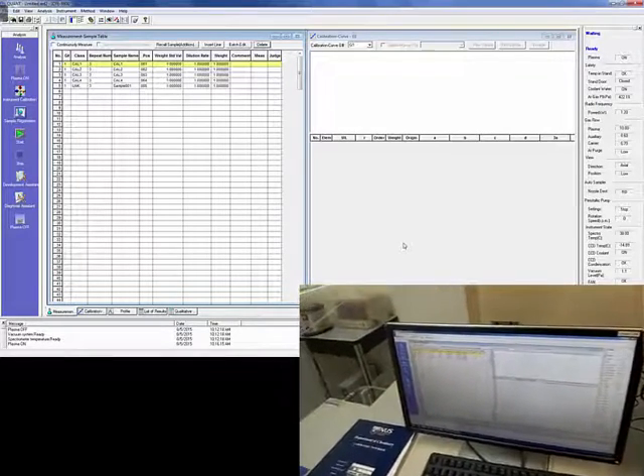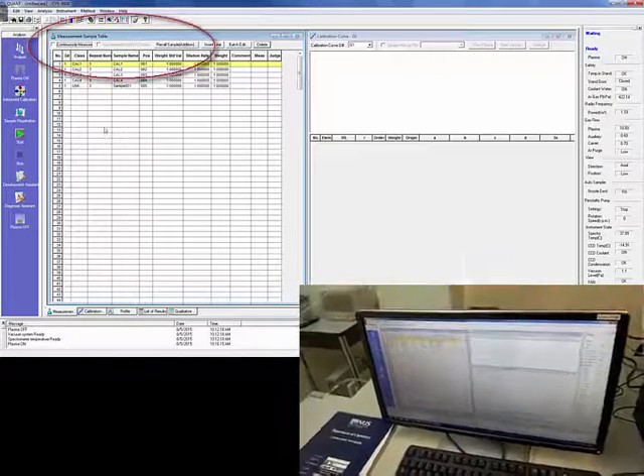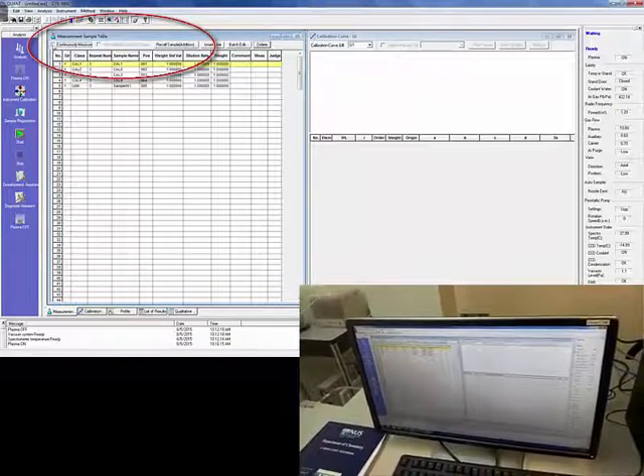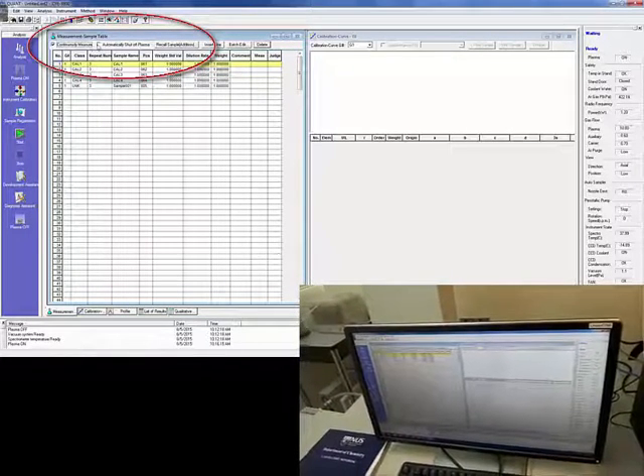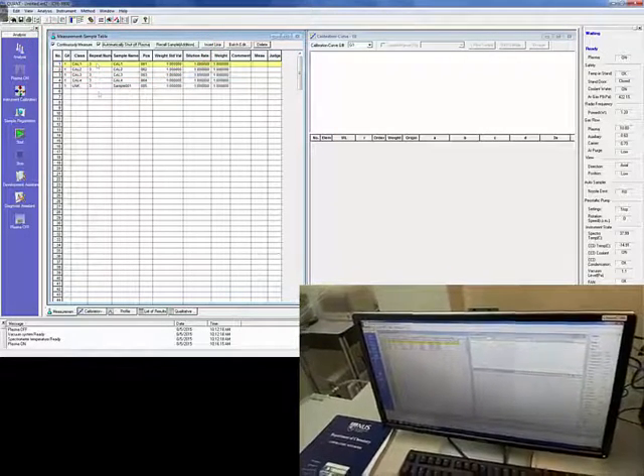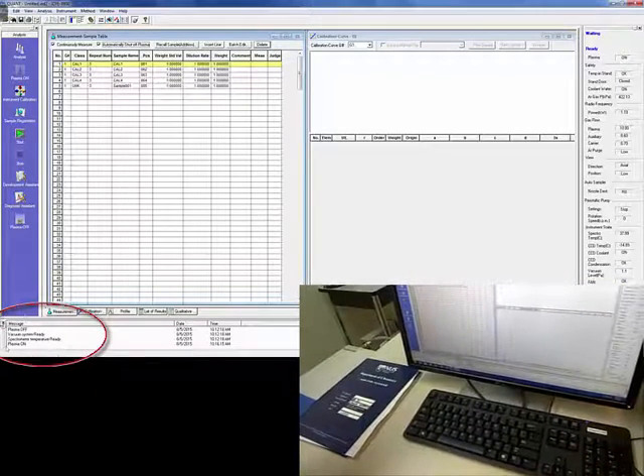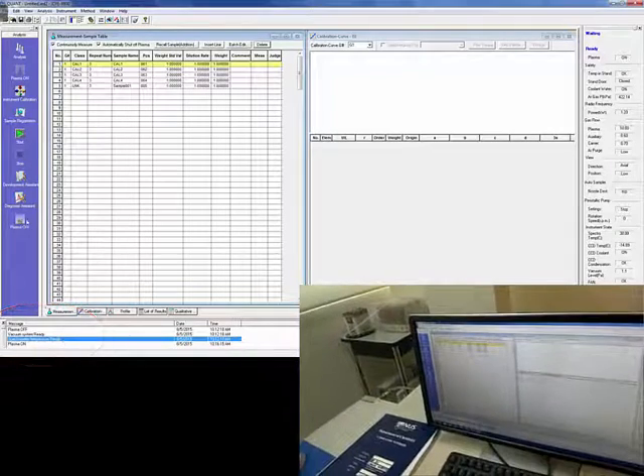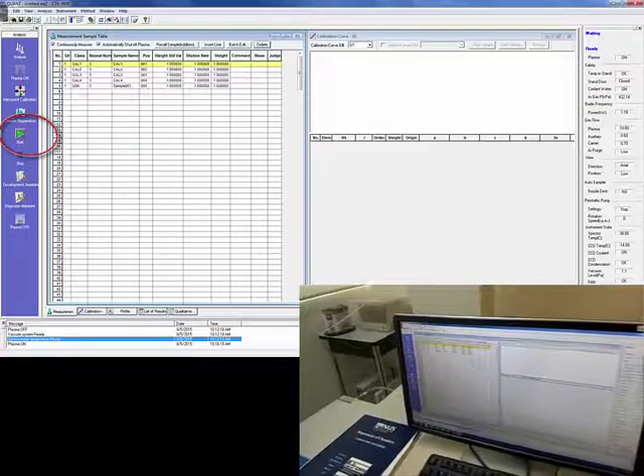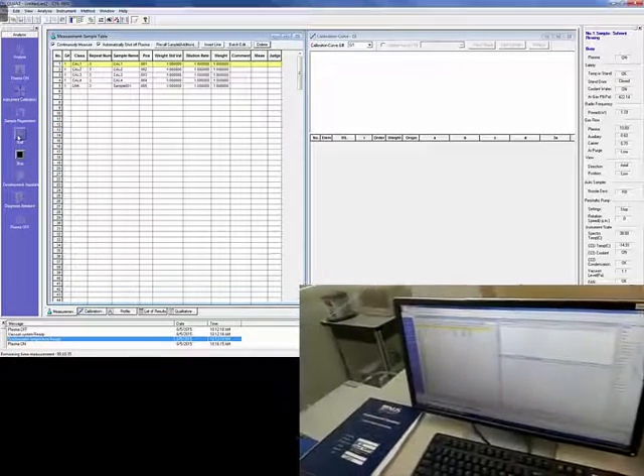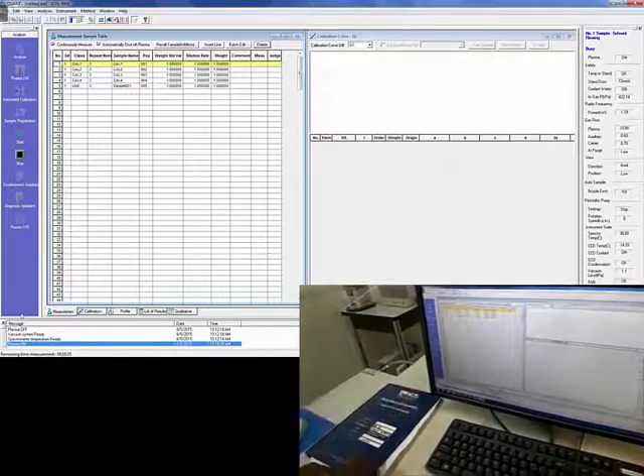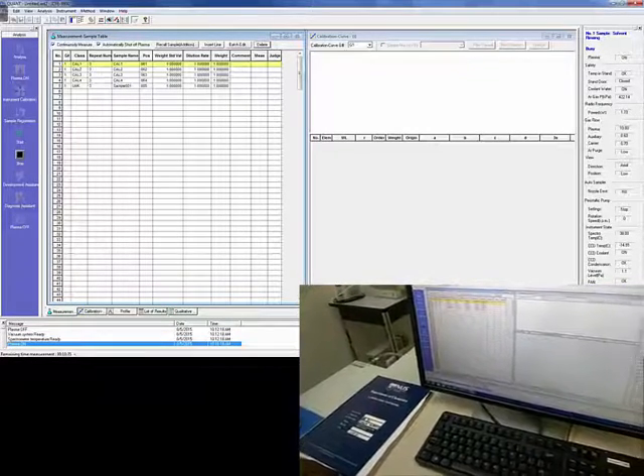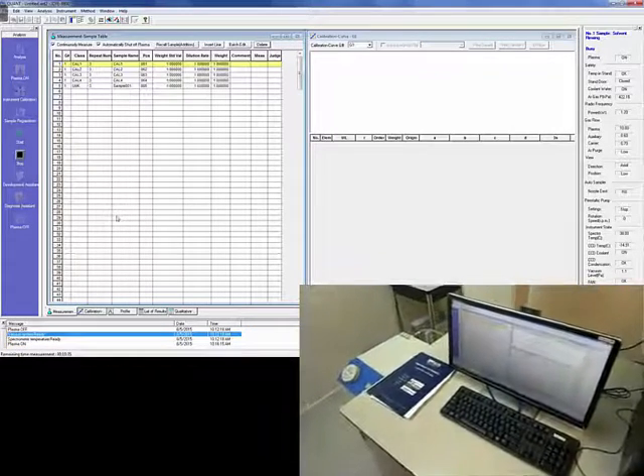Okay. So the next stage is actually to tell it to start. So what we will do is—we're using an autosampler—we'll click continuous measurement and we'll click automatically shut off plasma after it's finished the run. We're all now sorted. Down here, you can see the system information. All we need to do is press start. And it then is telling us that it is remaining time for measurement, 10 minutes. Okay. We're going to get a cup of tea while this is doing that. See you in a minute.